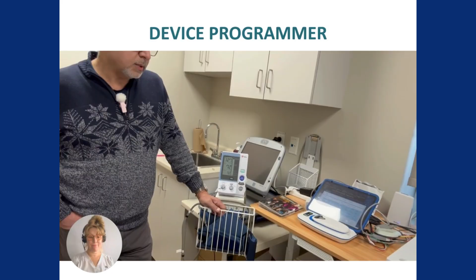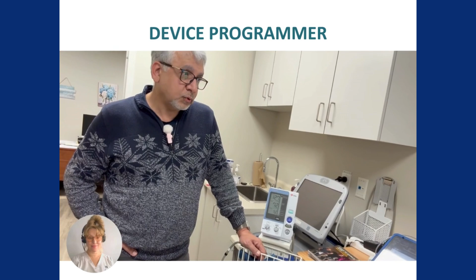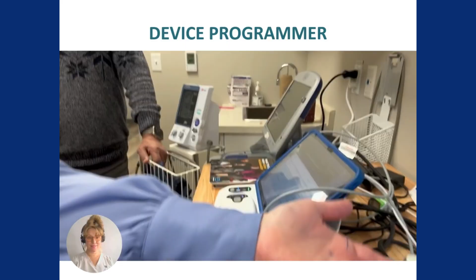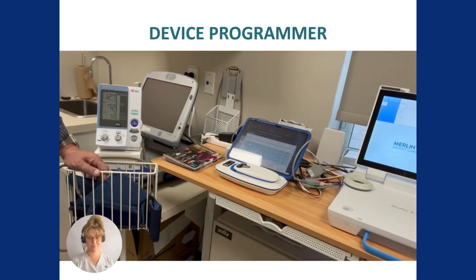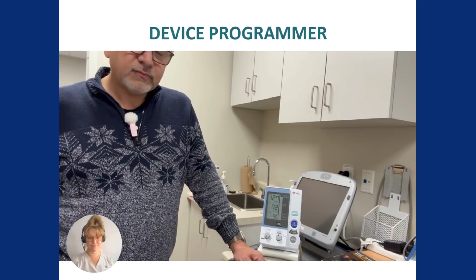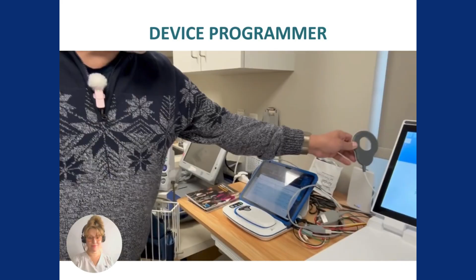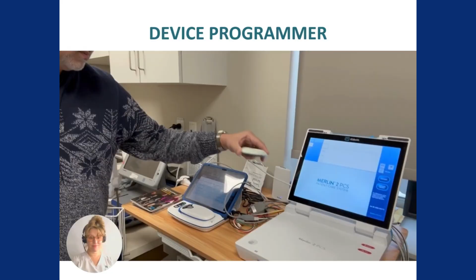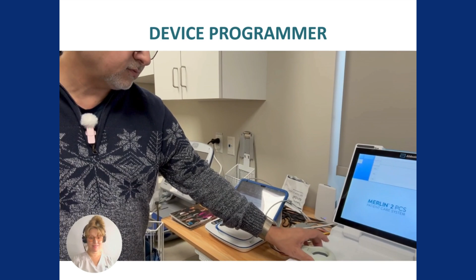Normally they have good parameters in the pacemaker, but sometimes we can find some abnormality in the rhythm, or abnormality in the function of the pacemaker, and more importantly, we can measure the longevity of the pacemaker. Longevity means how much life is left in the pacemaker. Is that the magnet you put over it? Yes, this is related to this machine, this programmer, and we put this on the patient's skin over the pacemaker, and it transfers the data from the pacemaker to the system.